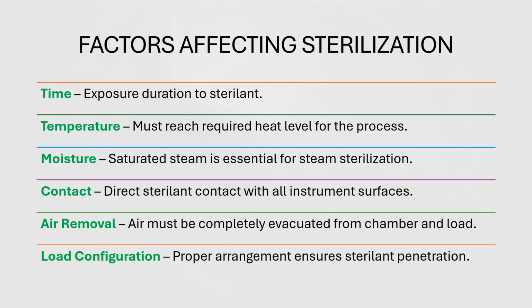Time. This is where the instruments must be exposed to the sterilant for the full validated cycle time. When we talk about time, we're not talking about the whole time it takes for the whole load to run. We're talking about the time for it to be in the sterilization phase. When we talk about a 4 and 30, we're talking about a 4-minute sterilization time and a 30-minute dry time. Or we might talk about a 10 and 45, a 10-minute sterilization time and a 45-minute dry time. The first number is the exposure time. Those instruments must be exposed for that 4 or 10 minutes throughout the whole length for the sterilant to actually be effective.